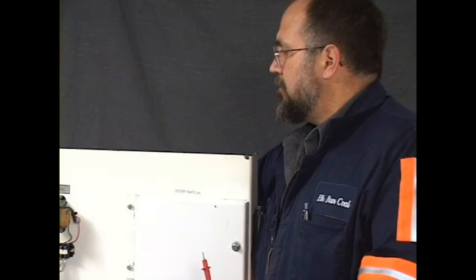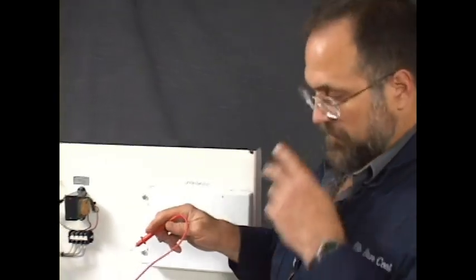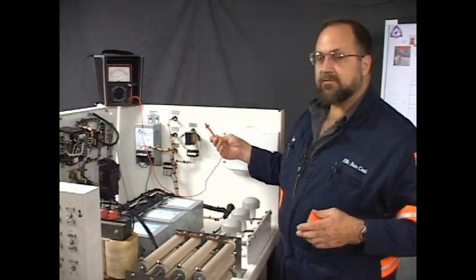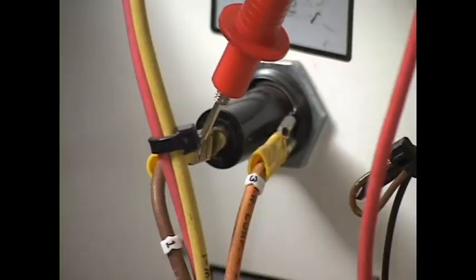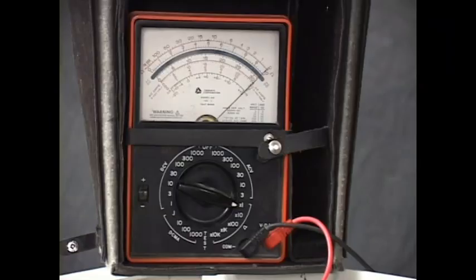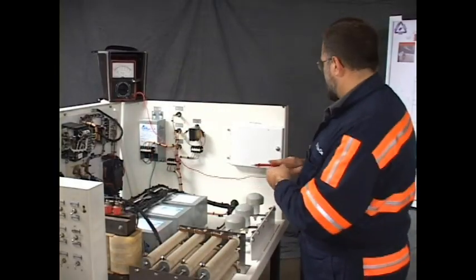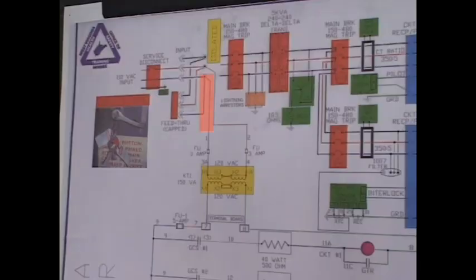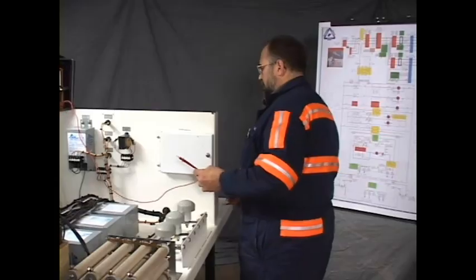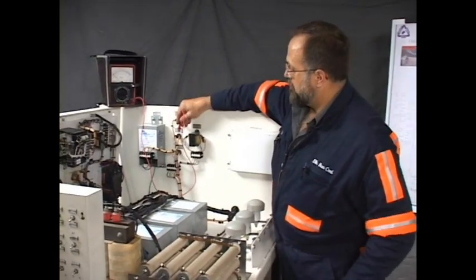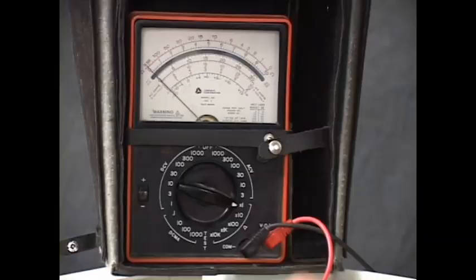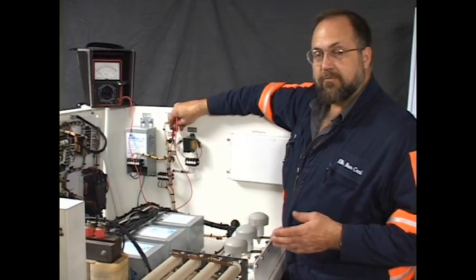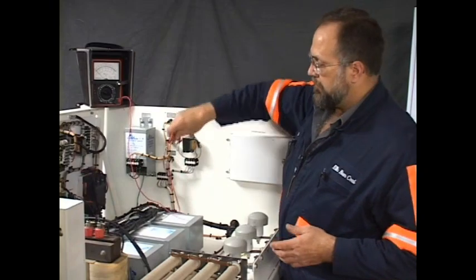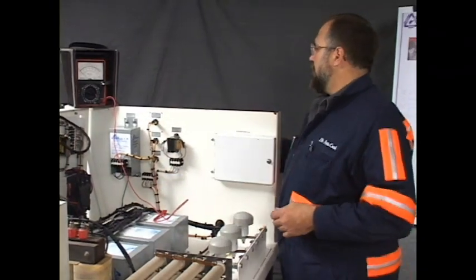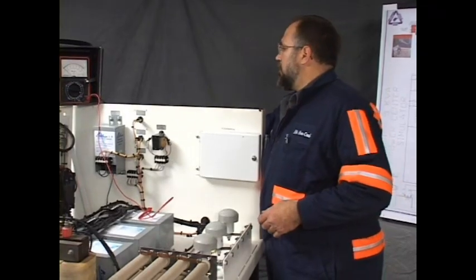As a more realistic problem that an apprentice may encounter underground, I'm going to disconnect the fuse, and for troubleshooting purposes, this would be the same as if the fuse were blown. Wire number 1 reads intact, coming from the source. From here to wire number 1 at the fuse is good. Now I'm going to read through the fuse, as we did earlier. As you can see, it reads open. That would indicate the fuse is open. That's a more often encountered problem than having a wire open.